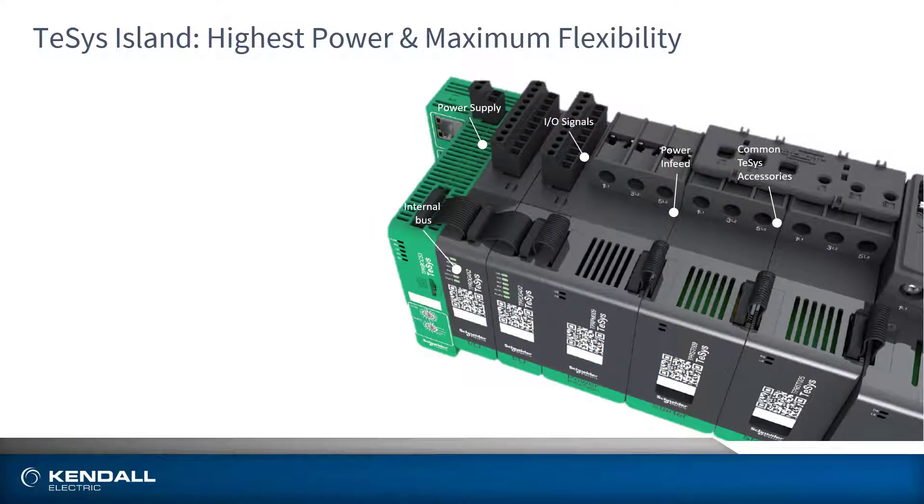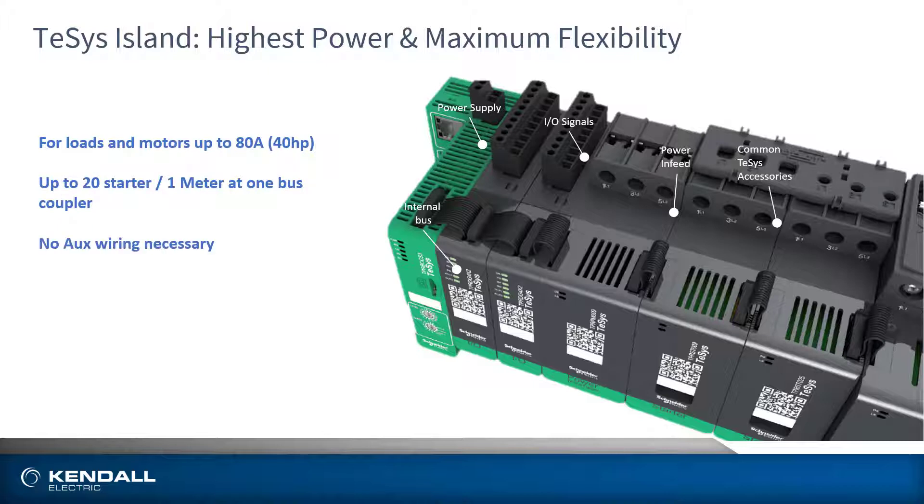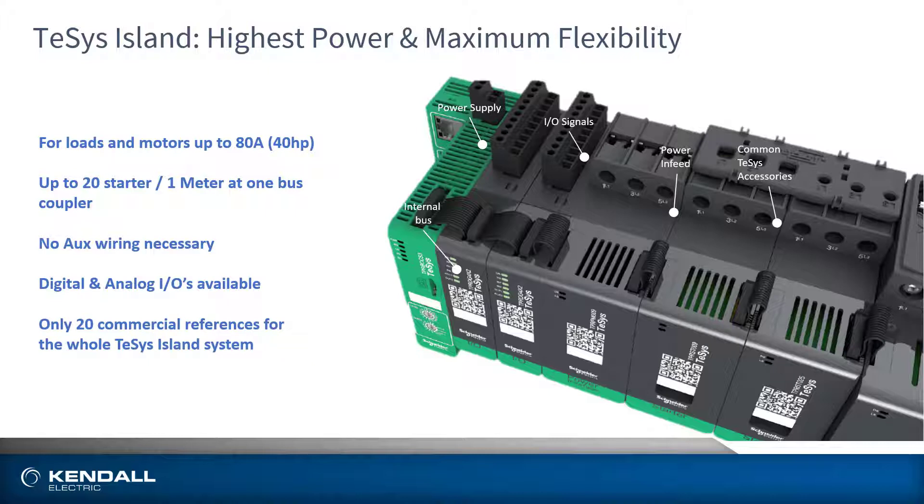The TeSys Island provides motor control for loads and motors up to 40 horsepower and 80 amps of total load, allowing for up to 20 starters on a single bus coupler or island. Through the use of the bus coupler, no auxiliary wiring is required, and capabilities of the island can be further expanded through the addition of digital and analog IO or safety.